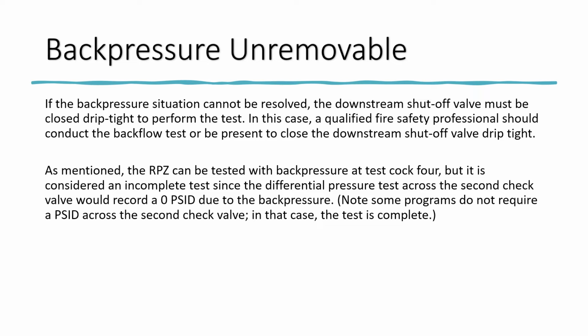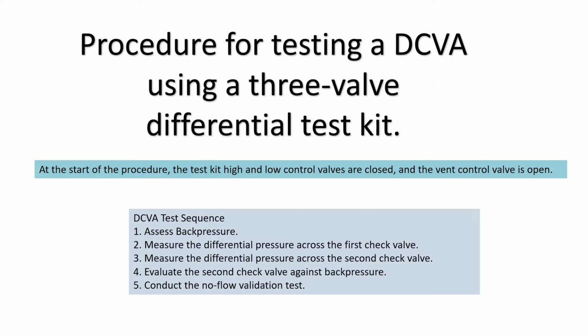Note, some programs do not require a PSID across the second check valve. In that case, the test is complete. Procedure for testing a DCVA using a 3-valve differential test kit. At the start of the procedure, the test kit high and low control valves are closed, and the vent control valve is open. DCVA test sequence.